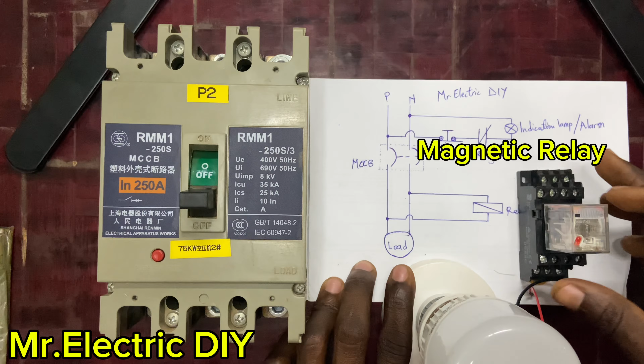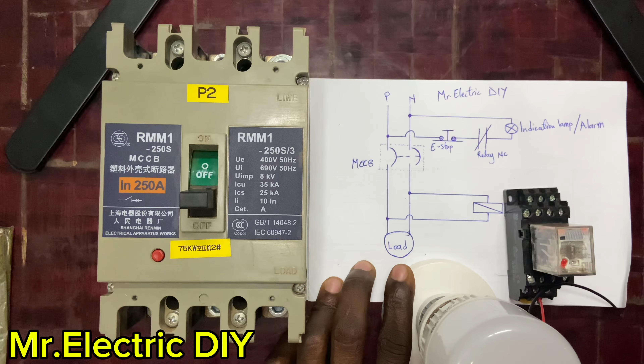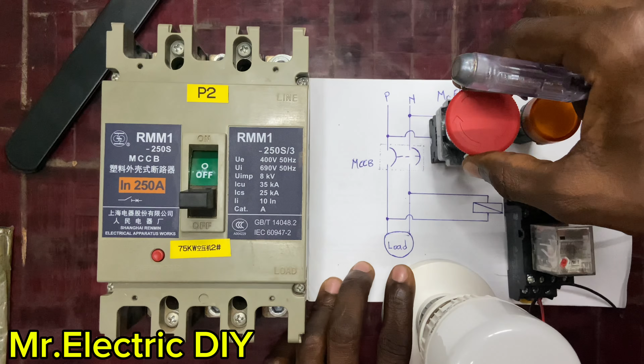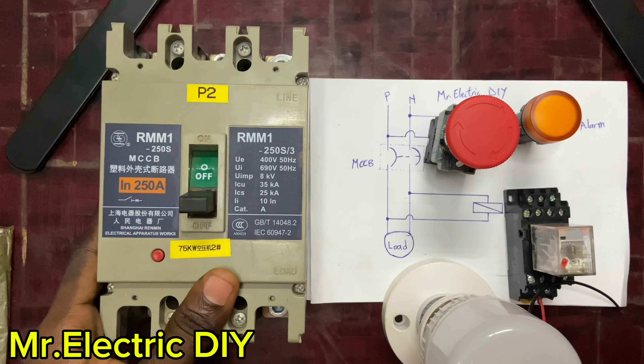And over here is the indication lamp or the alarm. If you have an indication lamp, you can use it, or even the alarm indicator, you can also use it. But in this case, I'm going to use an indication lamp. This is the lamp. And finally, the normally closed contact of this emergency stop push button. I have it here, the emergency stop push button. I'm going to use MCB to do these connections. I intentionally put this MCCB here to tell you that whether your main circuit breaker is either MCB, or any type of circuit breaker, it will still work.